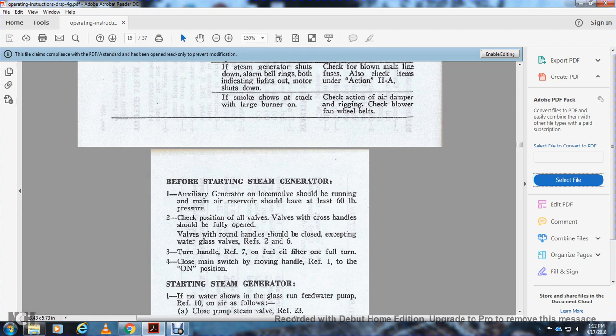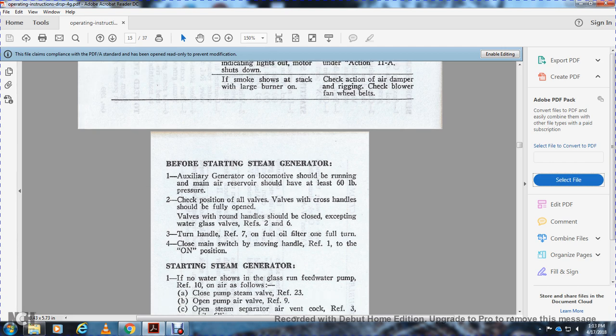Check the position of all valves. The valves with the cross handles should be fully open. Valves with the round handles should be closed, with the exception of the water glass valves, reference 2 and 6. Turn handle reference 7 on the fuel oil filter one full turn. Close the main switch by moving handle reference 1 to the on position.